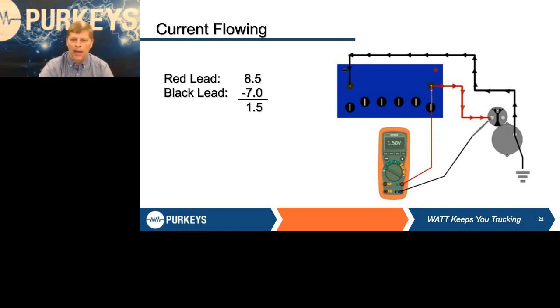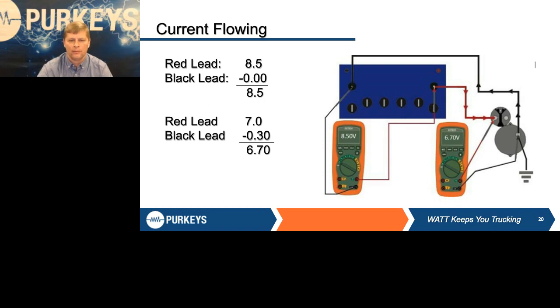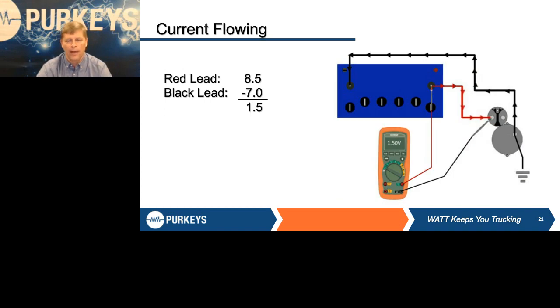Now, if you go back to the previous slide here and you stop and do the math, what's the difference between 8.5 and 6.7? Total is 1.8 volts. Now, if I look at what we did on the positive cable, we had a 1.8 volt drop total. I've got 1.5 in the positive, so what does that tell me I must have on the ground side? Kind of goes back to that algebra we took in school and we swore we'd never use. The basis is if you knew 2, you could always find the third one.